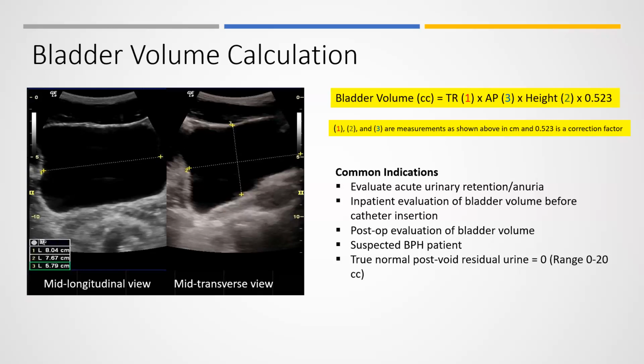Here you can see, and then you multiply all 3, and then you multiply that by a correction factor, which is 0.523. Some of the ultrasound manufacturers actually use this number as a correction factor to determine the volume of the urine inside the bladder. This formula can be used for anything that has a similar shape to determine the volume of that lesion, or if it's a fluid collection, you can use that. And there are some systems that have software built into it that when you select volume calculation and you calculate these 3, it's going to automatically determine the volume and display it on the screen for you.